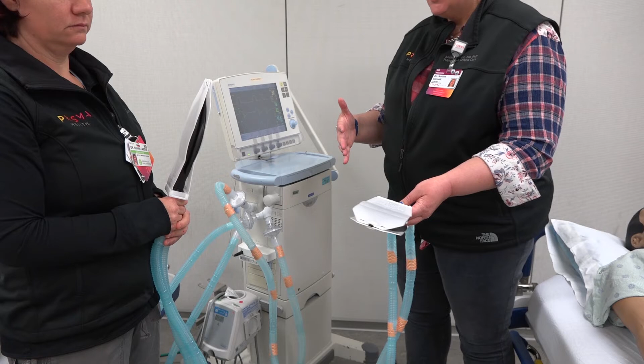Now, our leak is minimal on this, and now we're going to add the second test lung. And so the tidal volume is additive between patient A and patient B. And so my alarms were initially set for the total. You want to make sure that your alarms, so now we have to wait for 2 minutes to make sure our alarms are not going to go off. So now this has been 2 minutes, and so our alarms have come off, and as you see, we are not actually alarming anything. We don't have a leak in the system, so we are ready to actually attach it to our patients.